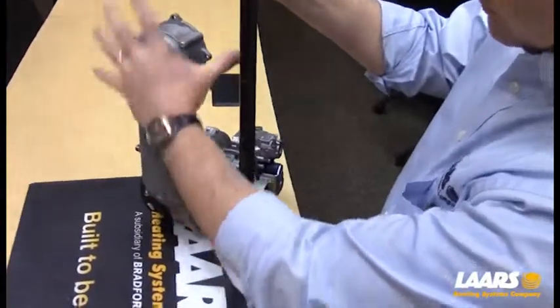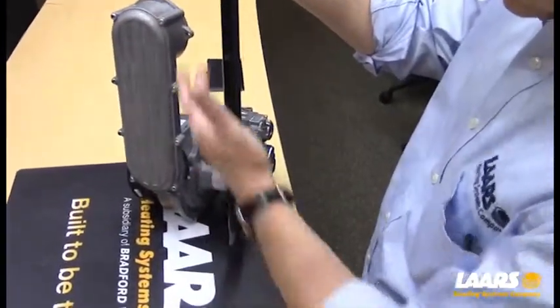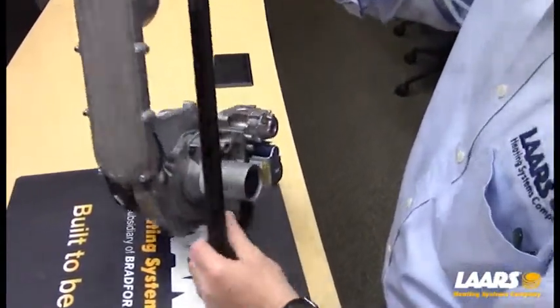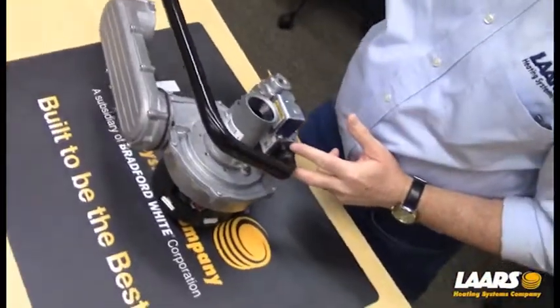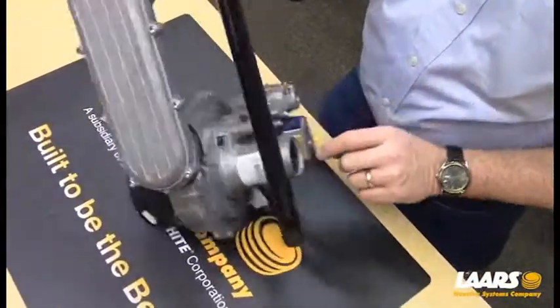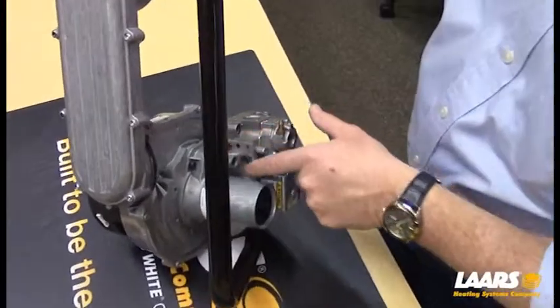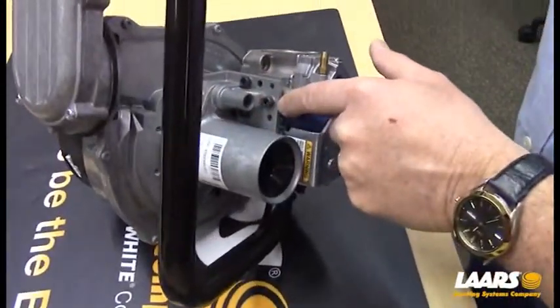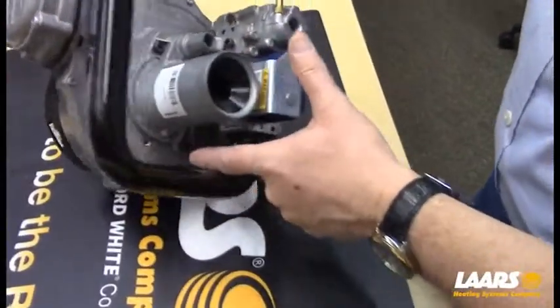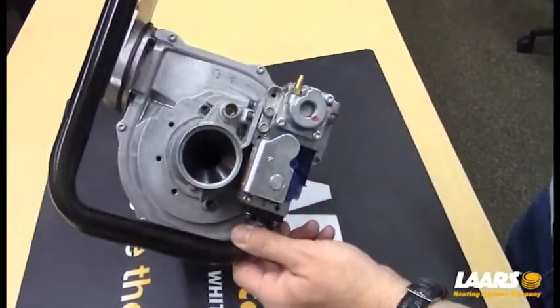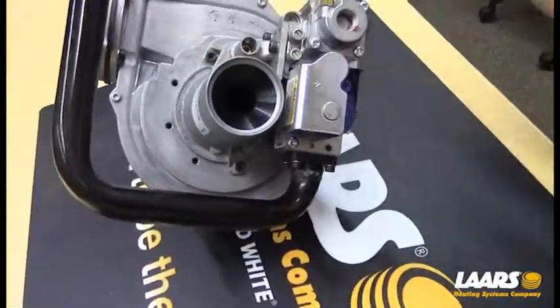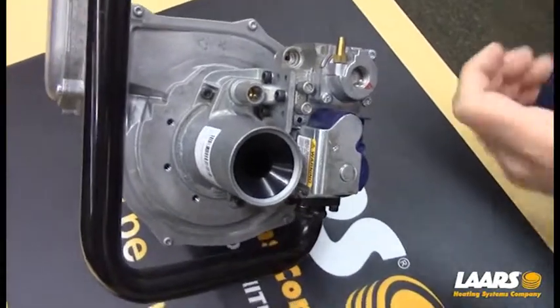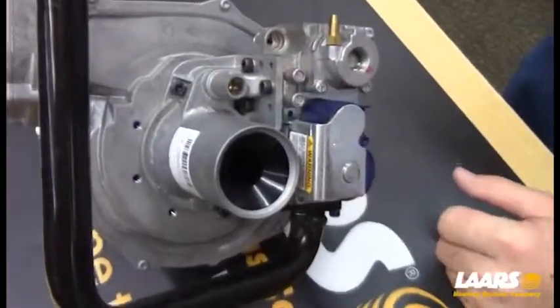This is where your arm is for the burner plate. Okay. We have the gas line that comes in, and that attaches to the bottom of the gas valve. The gas valve is attached to the venturi with 3 Allen screws. Okay, and the venturi is attached to the blower. And there are 2 Allen screws, one here, one here. Those are number 4 Allen keys that you would use to disassemble that.